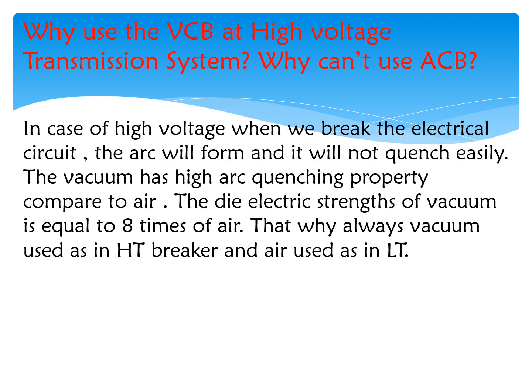Why do we use the VCB at high voltage transmission lines? Why can't we use air circuit breakers? In case of high voltage, when we break the electrical circuit, the arc will form and it will not quench easily because of high voltage and the current will continue to flow through the arc. The vacuum has very high arc quenching property compared to air. The dielectric strength of vacuum is almost 8 times that of air. That is why we always use vacuum circuit breakers in case of HT breakers and air is used in case of low tension.